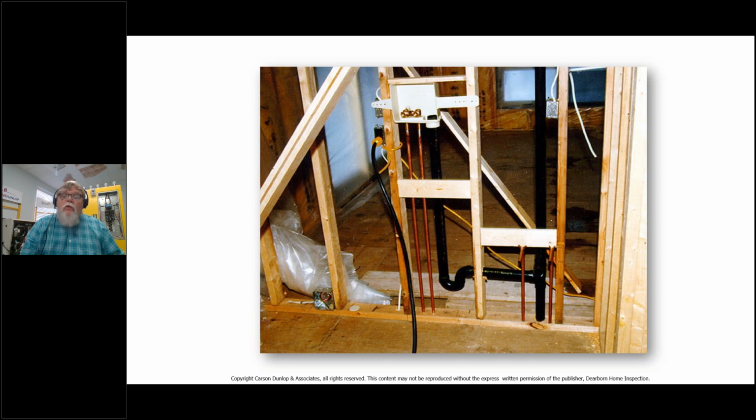This is pretty popular in some areas. We run into a wash machine drain, but the way you do that, and of course you're going to end up treating this water, the best way to do that would be to put a fitting in the standpipe, run up to the wall. You can put a box in the wall, and then you actually bring the condensate drain from overhead. We have a lot of attic installed units, so we see this pretty regularly here. And what you do is you bring the condensate drain through the top of the box. When it's all framed in, it looks nice and neat, and the water again can drain. It's going to go down the drain, so the city's going to have to treat that water, or your sanitation department is going to have to treat that water.